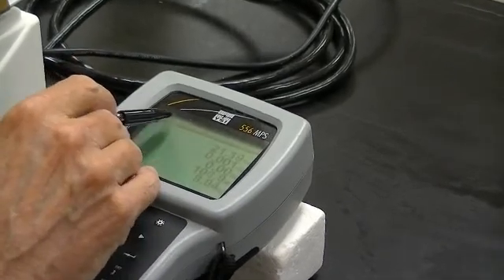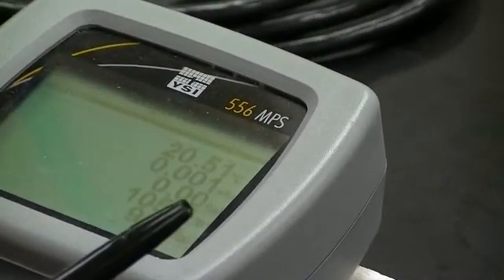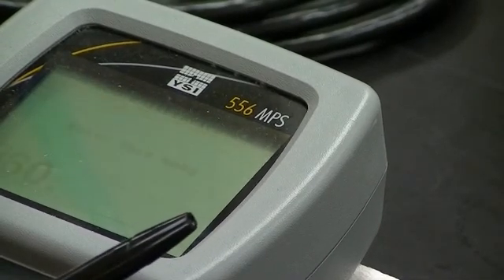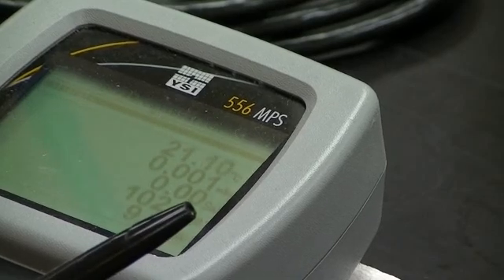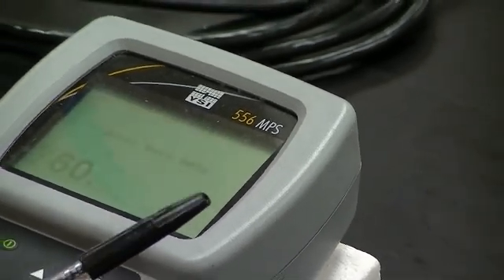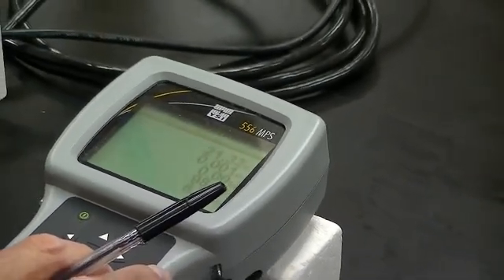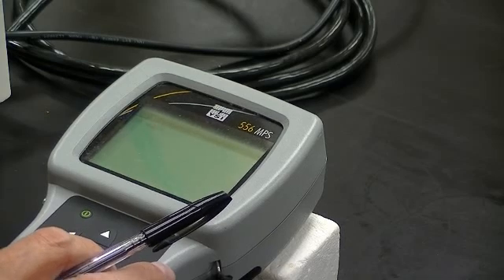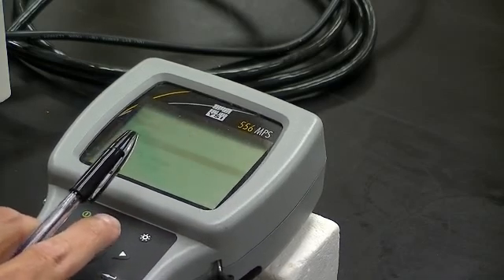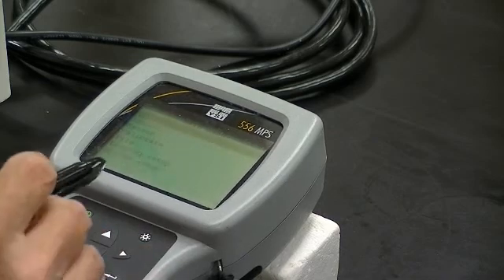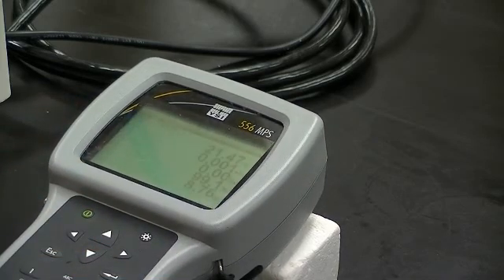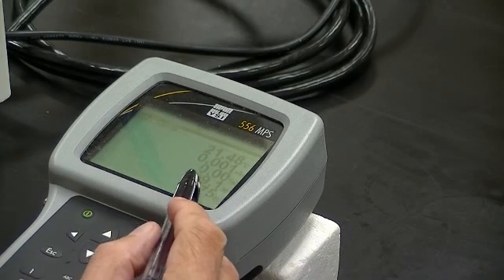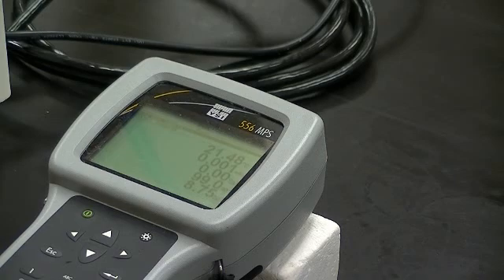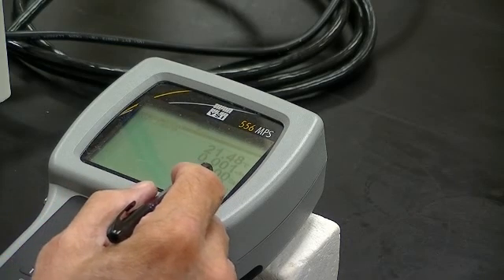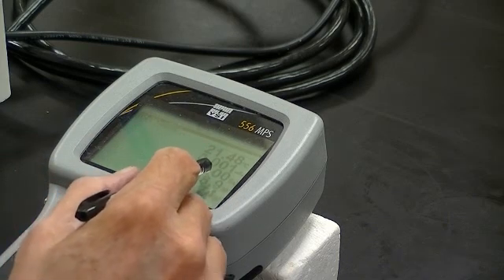And then it says continue in that highlighted line right there. And so you escape again, escape again, escape again, escape back to your main menu. Okay, so you escape back to the main menu, and then up arrow till it says 1, and hit return, and you're back to your main menu. And now this says 99.1%. Again, you would give it a little bit more time, and it should say very close to 100. The second number from the bottom.